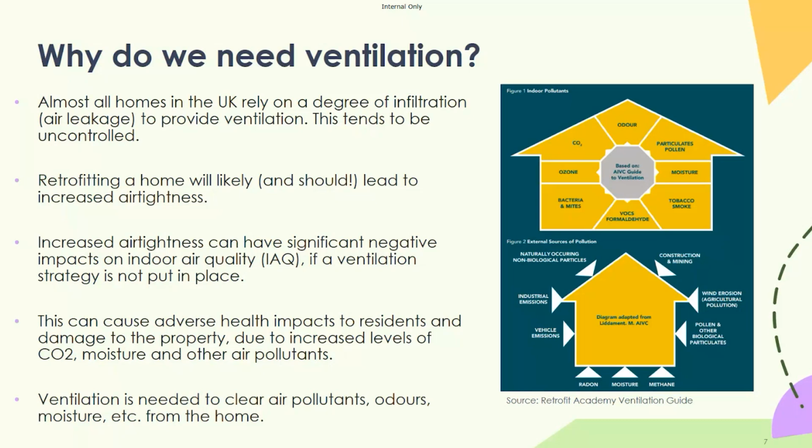It's absolutely correct that we should be chasing the utmost levels of airtightness. We should be trying to make our buildings as airtight as possible in the interest of energy efficiency and eliminating any uncontrolled air leakage. There is nothing wrong with that, regardless of building type or construction or age or conservation status. We should be pursuing buildings to be as airtight as possible, but then we need to be complementing that with a suitable ventilation strategy. So continuous extract being the most obvious solution that's readily retrofittable.